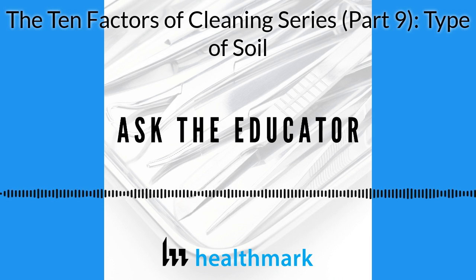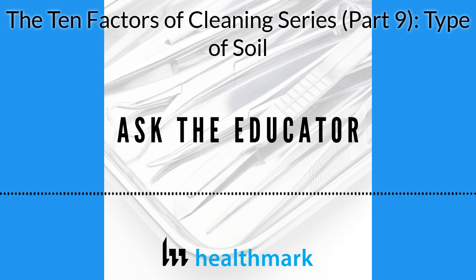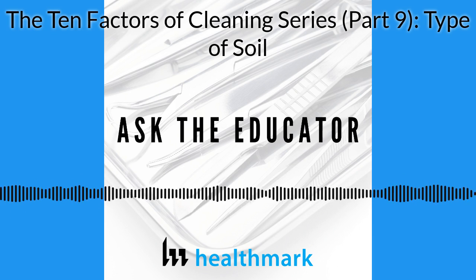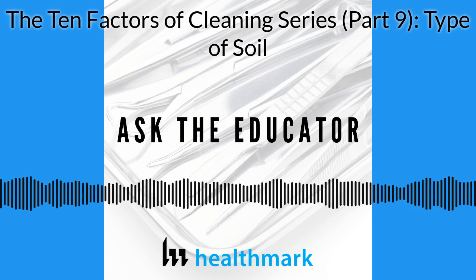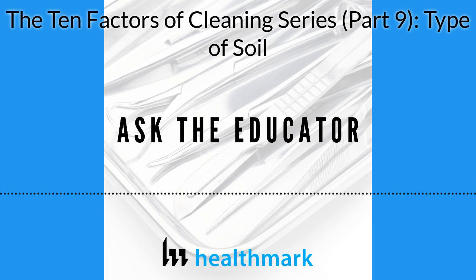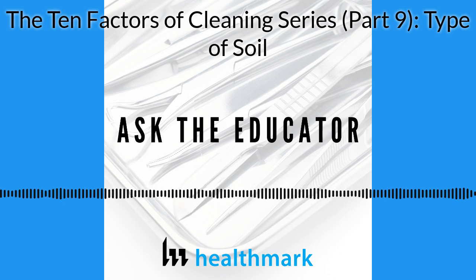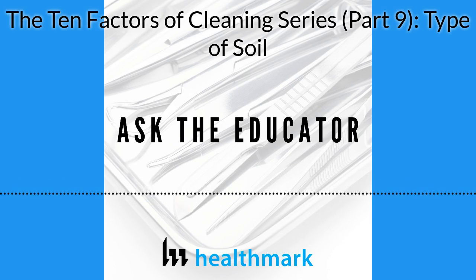I was also at a facility where the staff took alcohol, and they would wipe the instrument on the assembly side with alcohol because they thought it was hard water and they thought the alcohol would do something. Well, lo and behold, that spot, I tested it, was really residual blood. And by them using alcohol, that denatured it more. That problem showed up later after the sterilization process. That alcohol didn't fix it. So you've got to know your process and your chemicals.